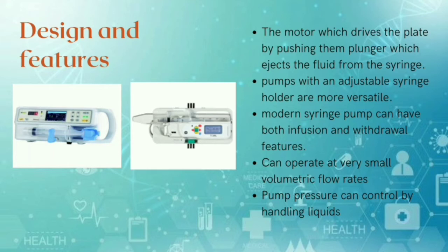Some modern syringe pumps can have both infusion and withdrawal features and multiple syringes. These devices can operate at very small volumetric flow rates while offering pulsed flow with high accuracy in delivery. In the syringe pump, pressure can be controlled when handling liquid with high viscosity.